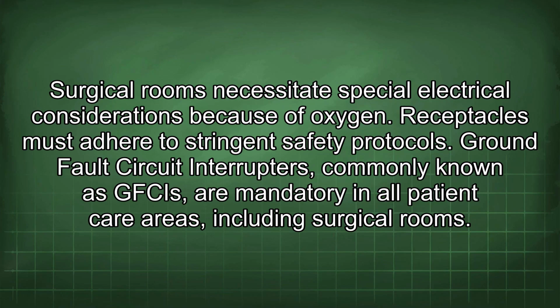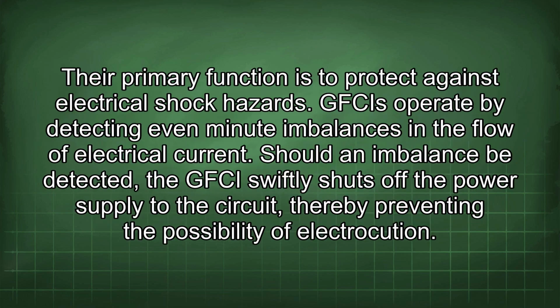Surgical rooms necessitate special electrical considerations because of oxygen. Receptacles must adhere to stringent safety protocols. Ground fault circuit interrupters, commonly known as GFCIs, are mandatory in all patient care areas, including surgical rooms. Their primary function is to protect against electrical shock hazards. GFCIs operate by detecting even-minute imbalances in the flow of electrical current.